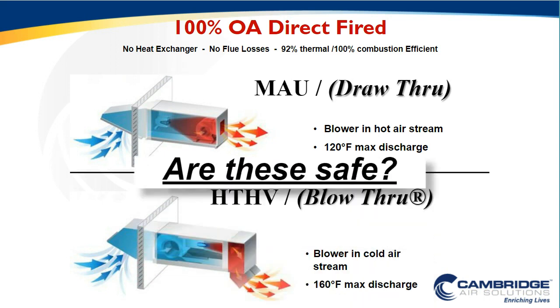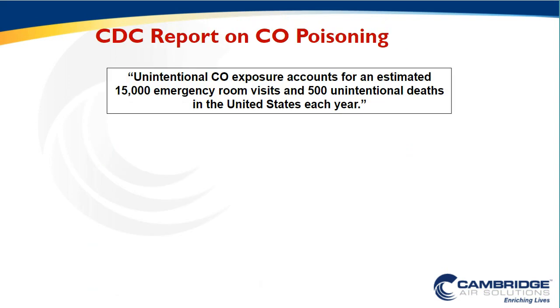How is it safe for either these makeup air equipment or the HTHV technology to deliver all the products of combustion into the space? And really, when we talk about safety with combustion equipment, the core concept for us to discuss is carbon monoxide. Carbon monoxide is one of the byproducts of incomplete combustion and can lead to unsafe conditions if not mitigated. So I'm going to talk about a report done by the CDC that looked at all the CO exposures in the U.S. What they found is that every year there are about 15,000 emergency room visits and about 500 unintentional deaths in the United States caused by carbon monoxide poisoning.